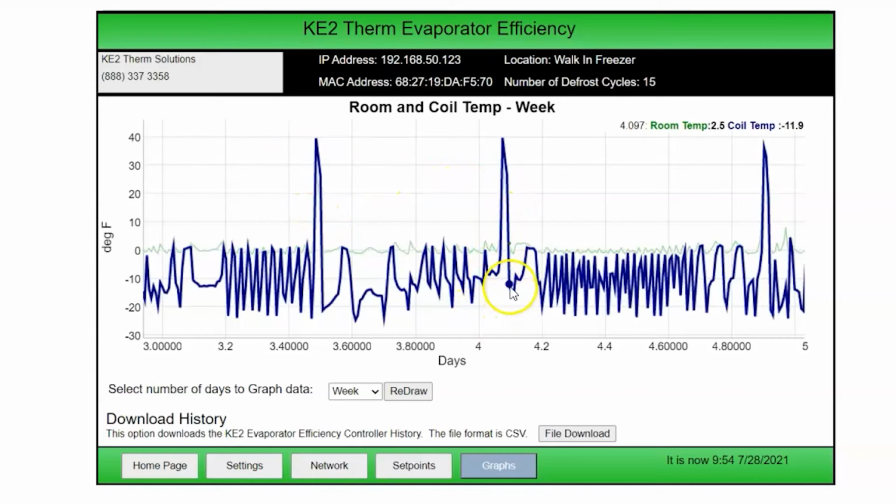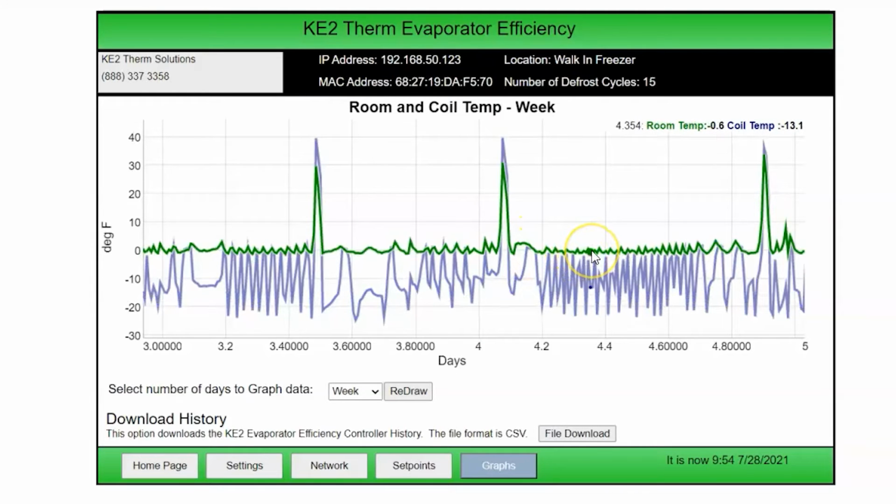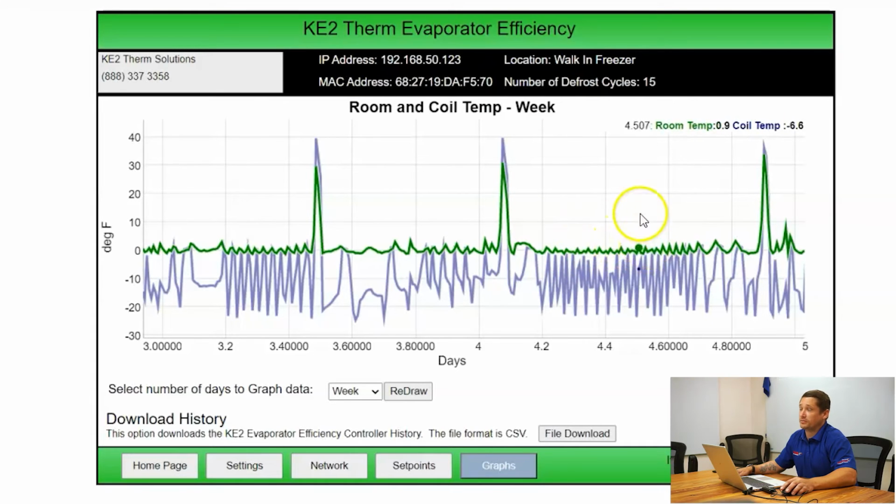Right now it's only going into about a defrost a day. Your typical mechanical clock goes into 4 defrosts a day, anywhere from 35 to 45 minutes. This one is reading the system, learning the system, and only activating defrost as needed. When a mechanical clock goes into defrost, it turns the heaters on and it heats until it's told not to. So the whole 35 to 45 minutes that it's in defrost, those elements are running.